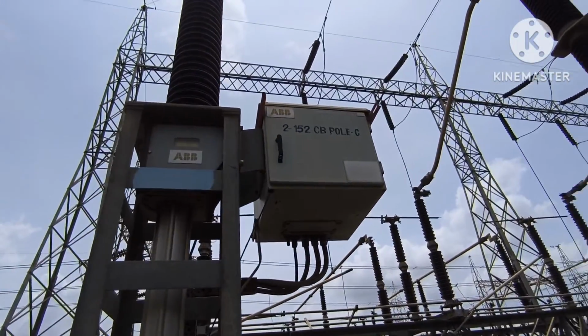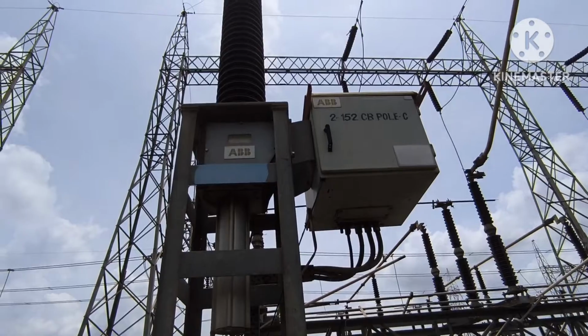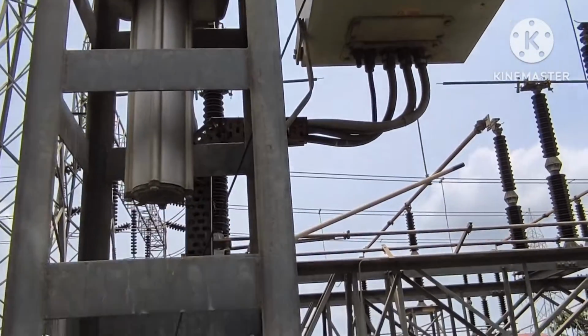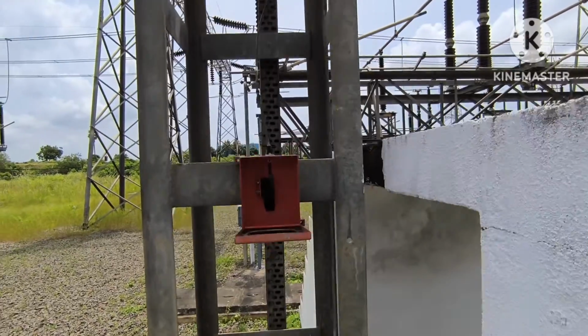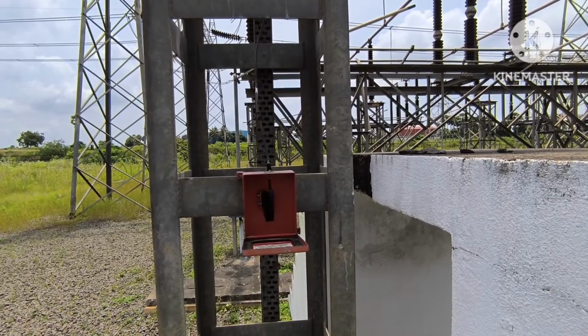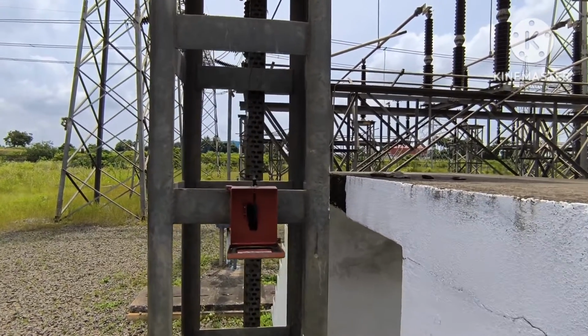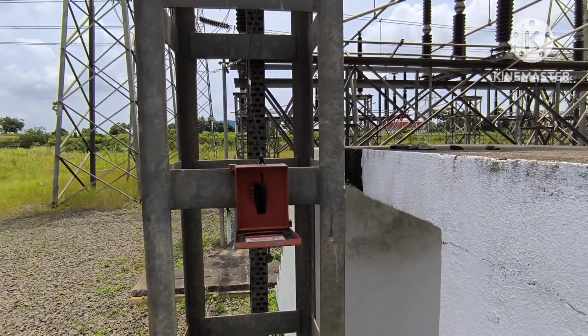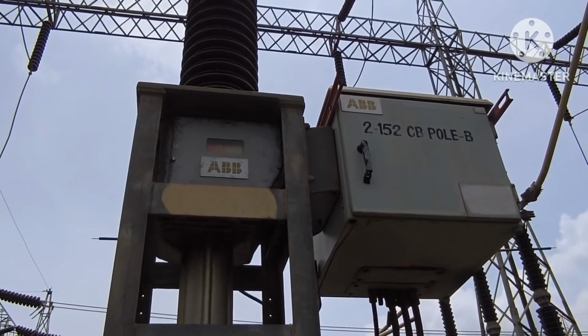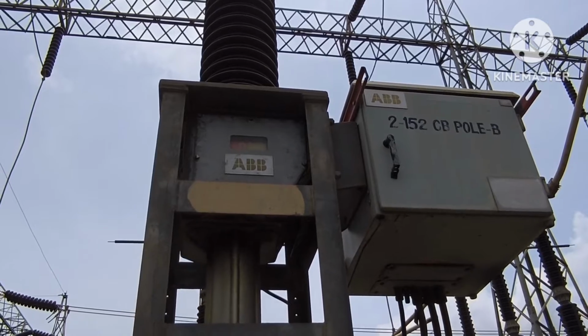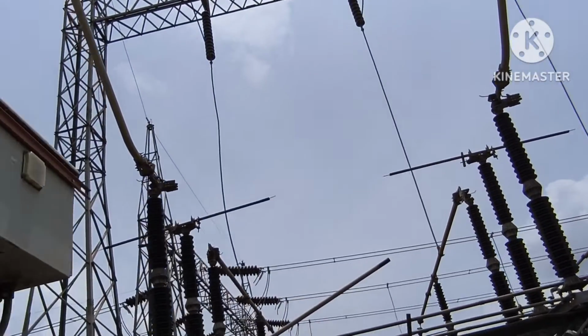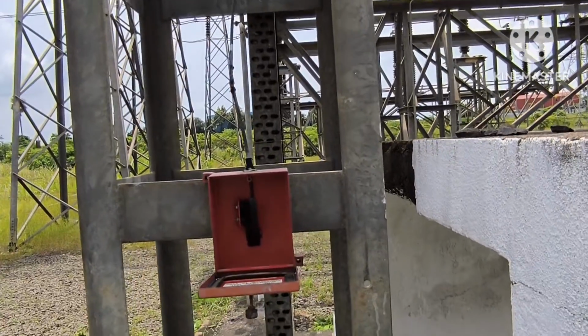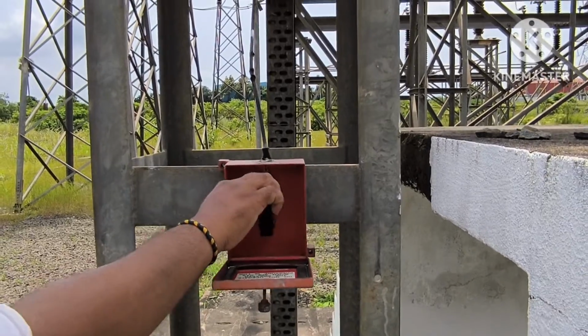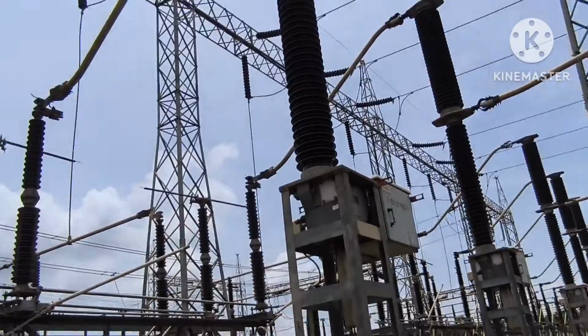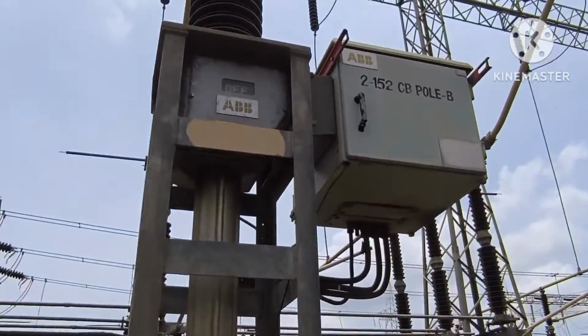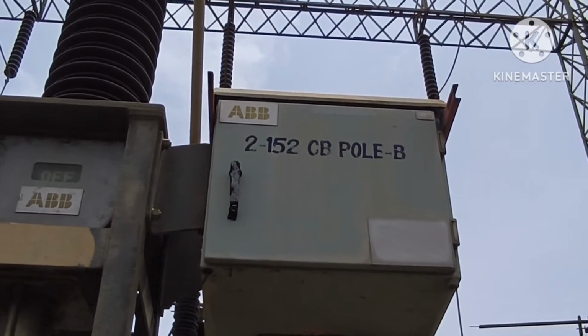Presently all three poles are in closed condition now. So, is it visible or not? Yeah. Now this is the mechanical lever, that is called the emergency tripping lever. So if we open one pole by operating this lever, automatically the remaining poles will be tripped. So I am tripping this pole now. B phase we are going to operate with that emergency lever. So if one pole is open, the remaining two poles will be opened by the pole discrepancy relay. That we are going to test now. So we are going to operate this lever. Now you see this one is open now. So the remaining two poles will be opened. They are already open now, you can see. The off condition is there. This is the use of the pole discrepancy relay.